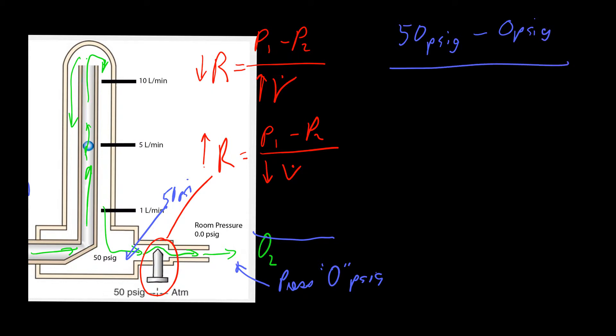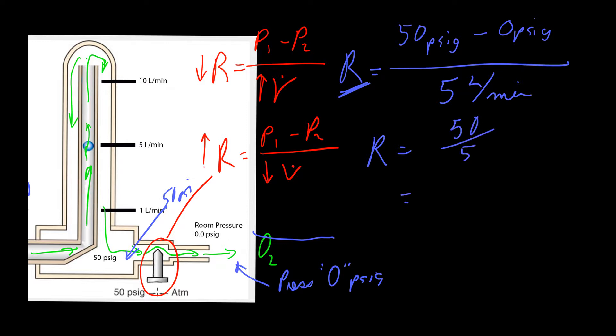Now we don't know what the resistance is, but because of where the ball is held within the Thorpe tube — and because this is precisely calibrated for 50 psi pressure gradients — we'll be able to know our flow rate precisely. At this time it is five liters per minute. So we'll be able to do the calculation and figure out what our resistance is. We can say our resistance is equal to 50 divided by 5, which equals 10 psi per liter per minute.